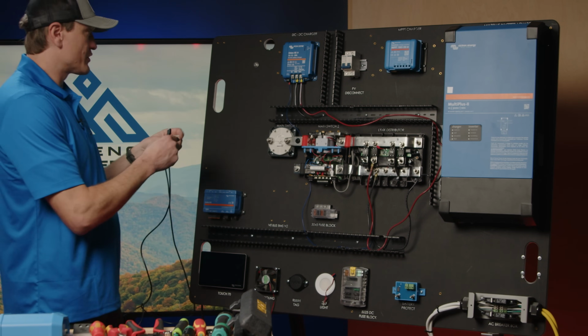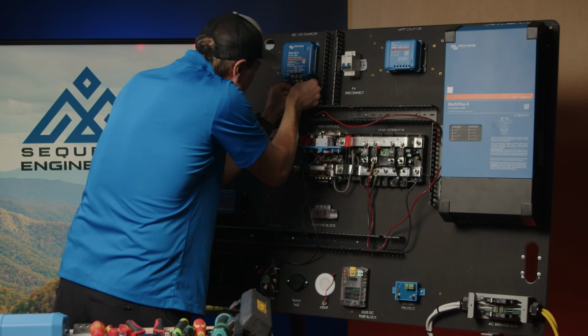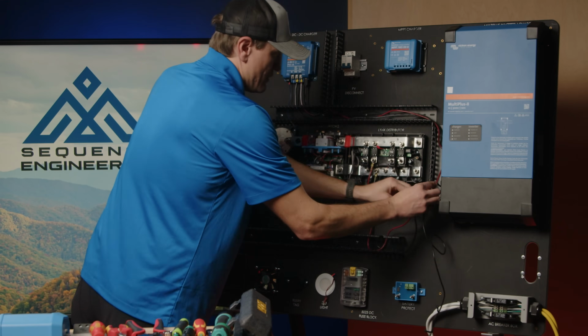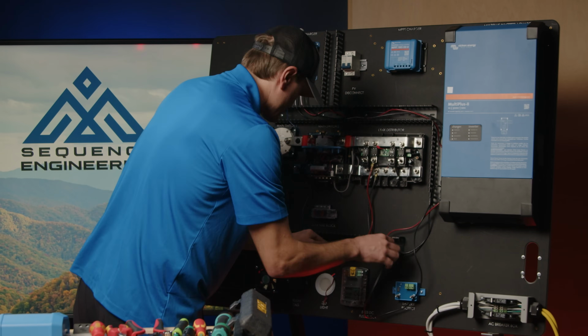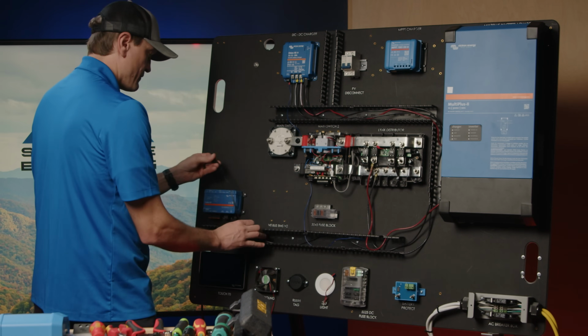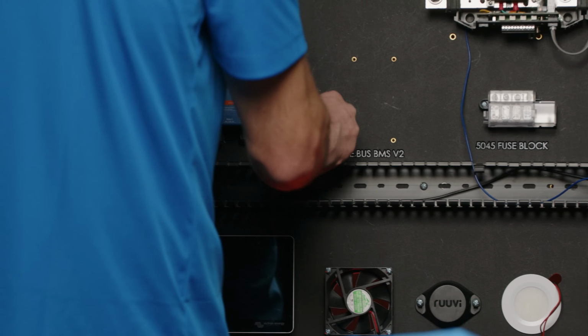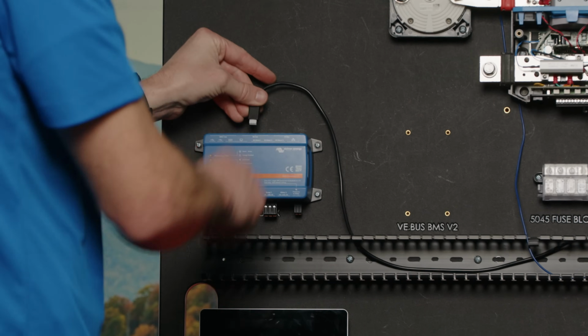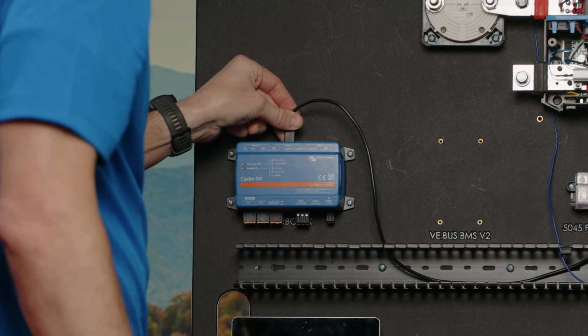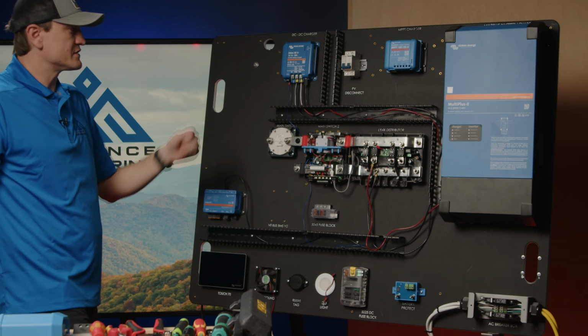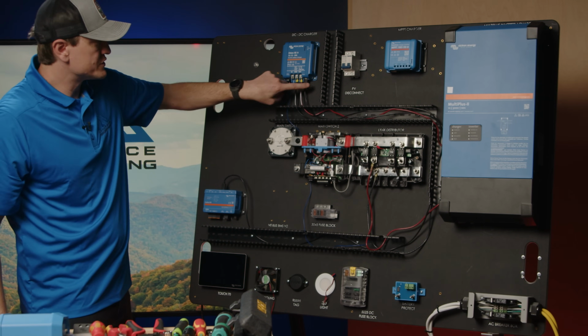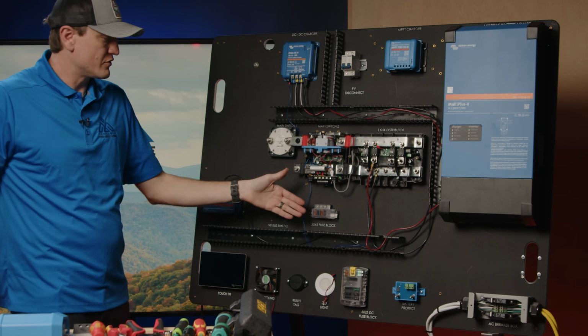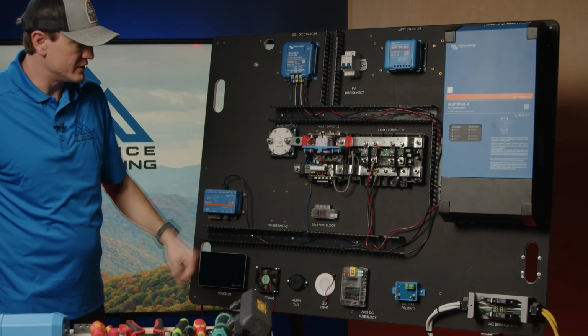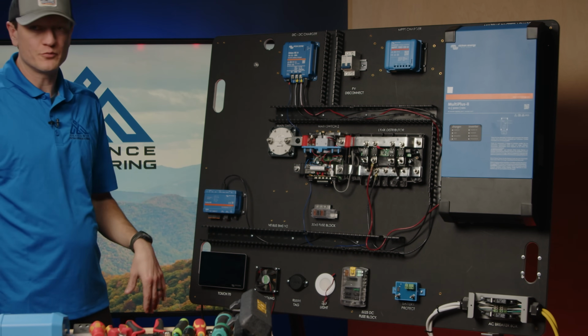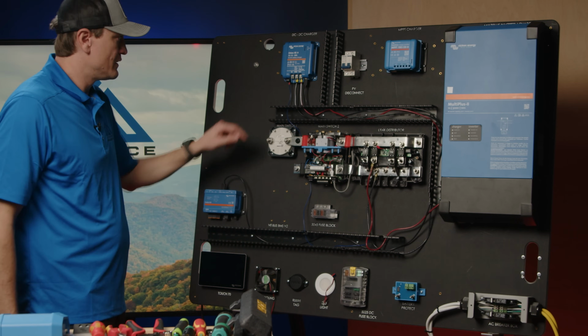So we're going to route this cable up out of our wire tray over to one of the three VE direct ports on top of our Cerbo GX and insert that cable. Now this device is being told what to do by our Cerbo GX, or the BMS can directly tell the charger to turn off via the allow-to-charge port on the bottom of the BMS.